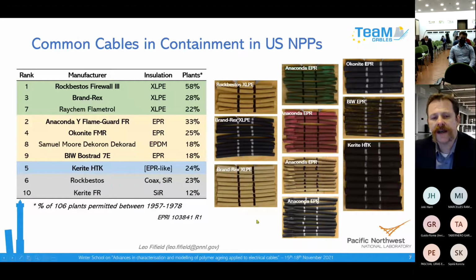My understanding is that similar materials are used in European plants, but not necessarily the same. In U.S. plants, almost all cables are XLPE, cross-linked polyethylene, or EPR, ethylene propylene rubber. We have very few polyvinyl chloride insulation examples. There's also silicone rubber, especially at higher temperature locations, but most cable insulations in the U.S. are XLPE or EPR. There's a variety of manufacturers - some of the most common being Rockbestos, Brand-Rex, Raychem, Anaconda, Okonite, BIW, Kerite.